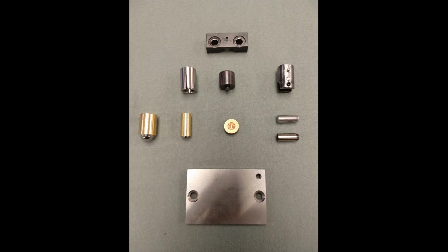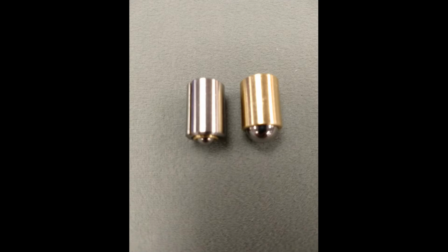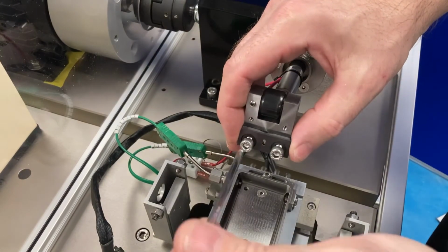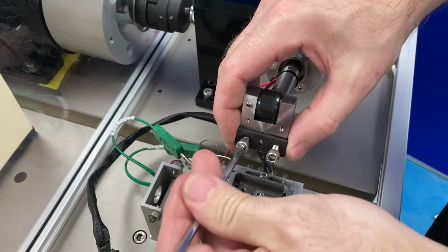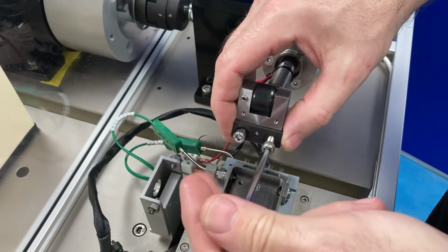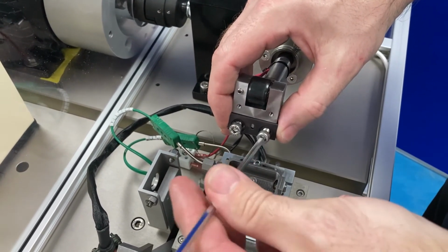Standard specimens include a 6mm ball, a 10mm ball, a 6mm diameter cylinder specimen, and a 12mm diameter area contact specimen. The 6 and 10mm ball specimens are carried in brass tubes, which aids handling and identification of wear scar location. The ball specimen carrier is attached to the reciprocating head using a clamp plate with a hemispherical seat.